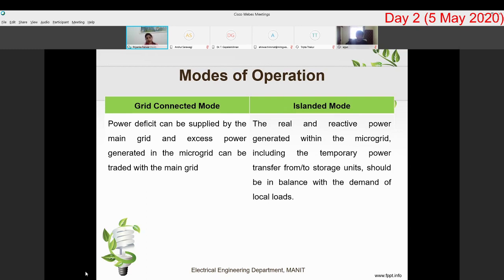However, if it is an islanded microgrid, it requires full control because now it is all by itself. If the load increases, the voltage and frequency will drop. If the load decreases, the voltage and frequency can go beyond the bounds. So the responsibility of maintaining the balance of load and generation is more critical in the islanded microgrid, and that has to be carefully managed.